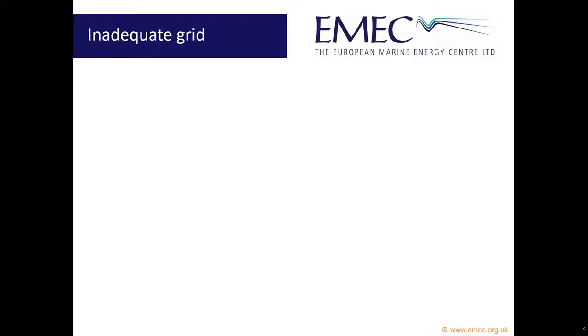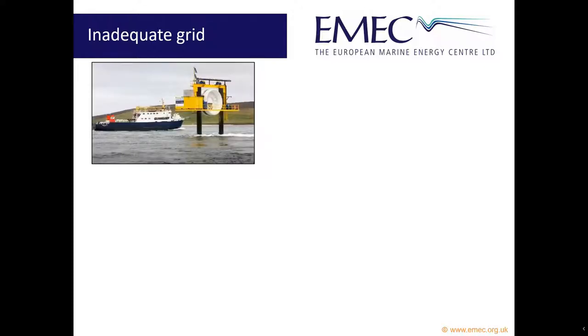So we've been spending time thinking about what can be done, trying to tackle things, because we've got some snags. How do we get the energy from that tidal turbine off the island into the UK supply? Orkney is the most northerly point on the national grid, but the cables we have are very small, and we've got about 60 megawatts of export capacity from the islands in total, running on two cables.